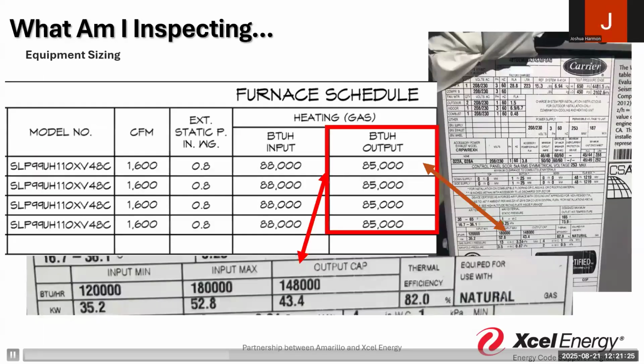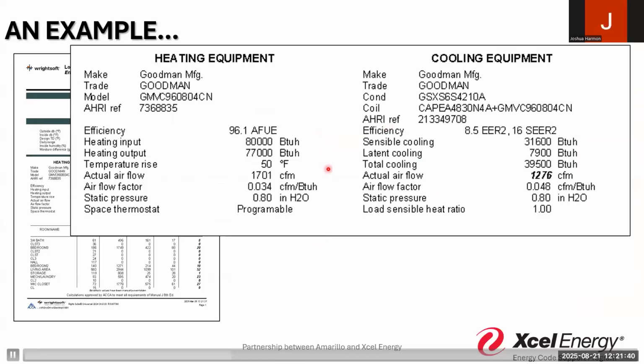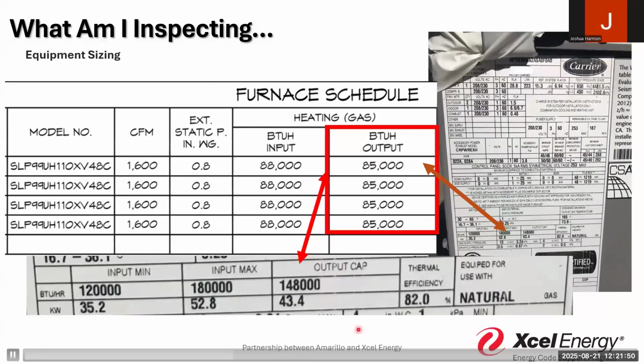What I'm not expecting to see is an 85,000 BTU system, or even 148,000 BTU. I'm expecting 85, and this is where we'd have consistent questions. I've got a heating load calculation that says 77 is what that equipment is going to do, but I've got a schedule on site that says 85, not 77. So somehow we picked a different piece of equipment. And when I'm in the building, I'm seeing it's twice as big as it was supposed to be, going from 77 to 148,000 BTU, and from 96% efficient to 82% efficient. Something has changed here.